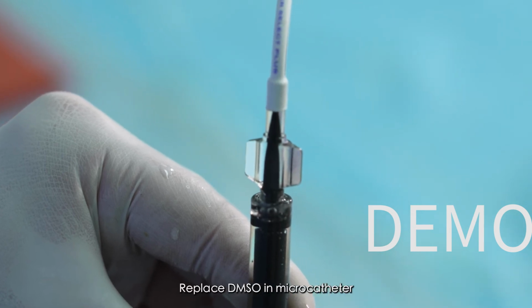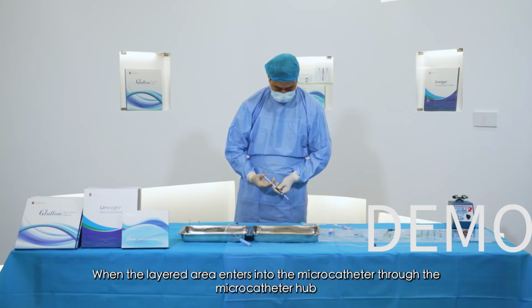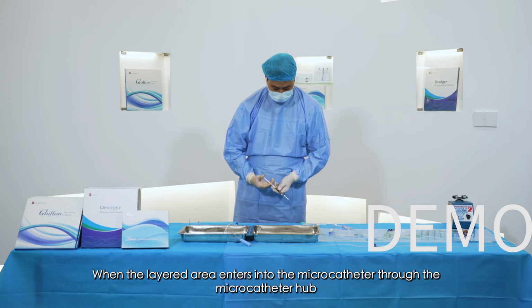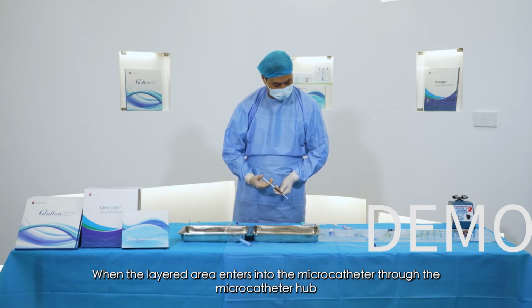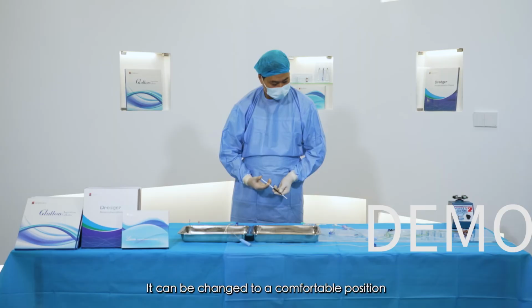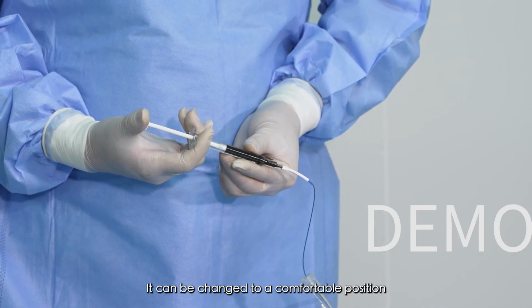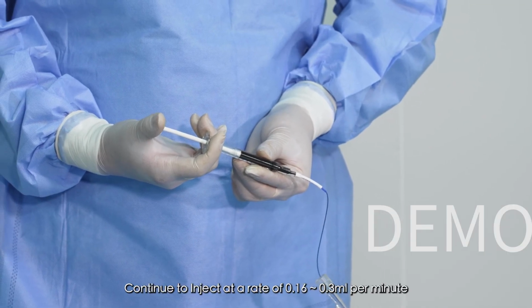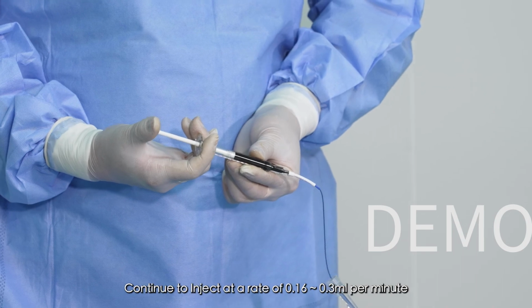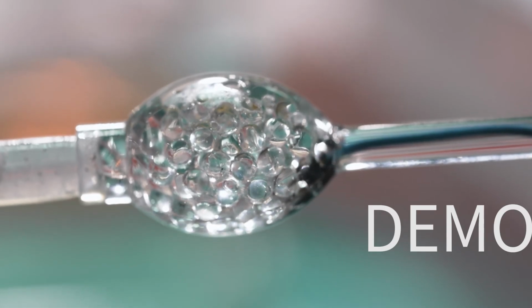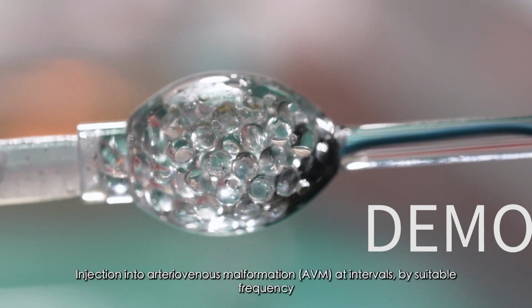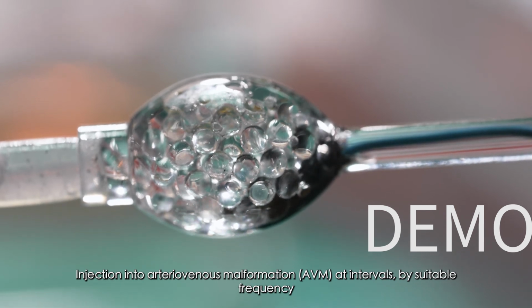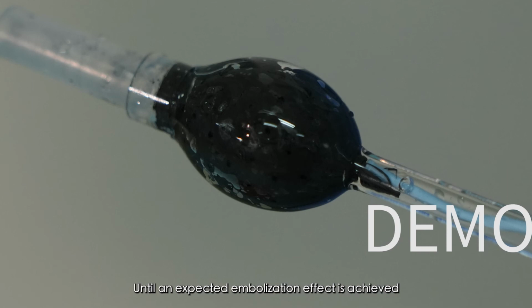Replace DMSO in the microcatheter. When the layered area enters the microcatheter through the microcatheter hub, it can be changed to a comfortable position. Continue to inject at a rate of 0.16 to 0.3 milliliters per minute. Inject into the arteriovenous malformation at intervals with suitable frequency until the expected embolization effect is achieved.